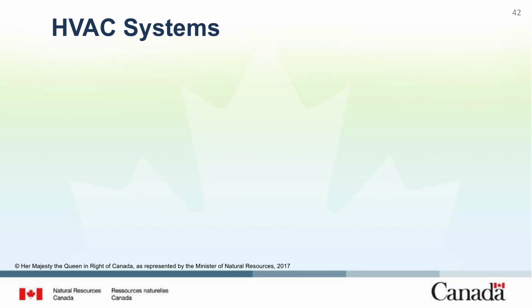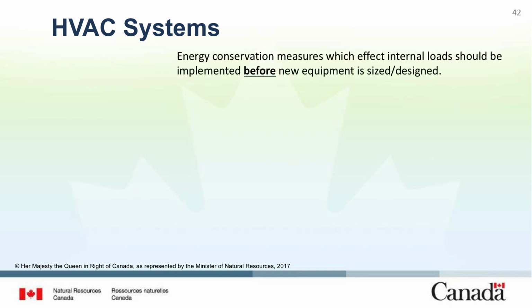Now, we've talked through the first three items: building envelope, plug loads, and lighting systems. Those systems should all be implemented before you look at HVAC considerations. You want to reduce your loads as much as possible, and it's not unusual to reduce your loads as much as 50% before addressing your HVAC system. Since most HVAC systems are oversized, it's not uncommon to put in new HVAC equipment that's less than half the capacity of what was there before. So as a first step, you should reduce your loads, and the second step is to implement efficient HVAC systems to serve those loads.